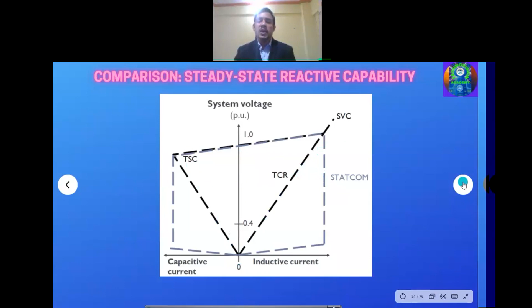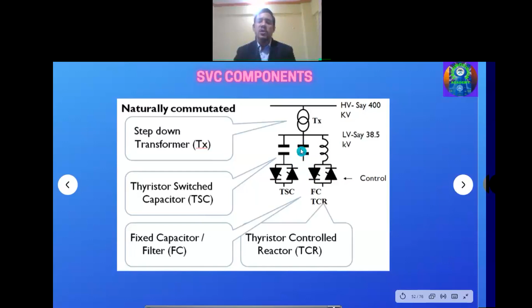So static var compensator has certain components. If I want to connect any static var compensator, there should be thyristor control devices. Here a transformer is required to connect with the EHV level, so a step down transformer is required. Then we have thyristor switched capacitors, which are operated by the thyristor modules. Then here it is a fixed capacitor, or we can say a fixed filter. Then we have the thyristor control reactor, TCR. And this is a fixed capacitor, no variable here. These thyristor modules are connected to it. It's a fixed capacitor, or it can act as a filter also. So these are the components.